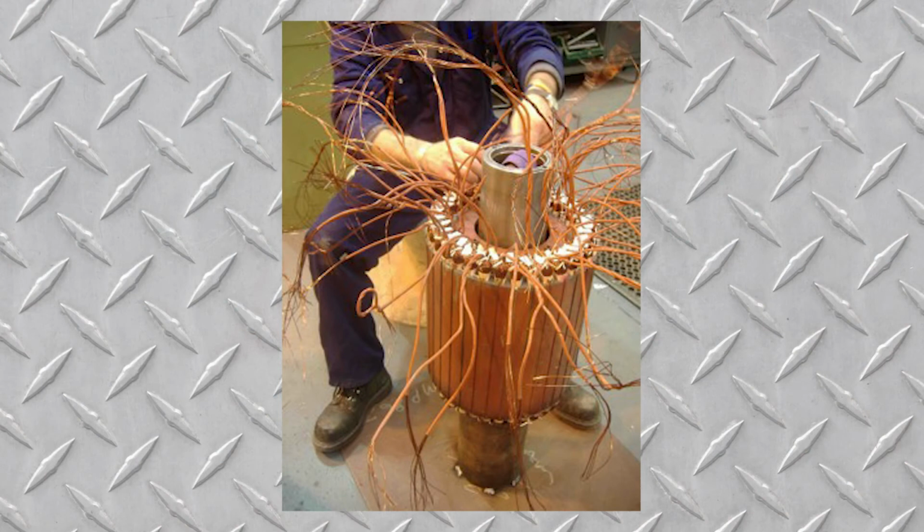Turns out that the speed with which you're doing things becomes what's important and is where the problems arise. If you're in a factory and you have an important motor go down, you need it back up as soon as possible. So you go to the rewind shop and you say, do it very quickly. And in order to do this, excessive temperatures are used, which can have several negative consequences.